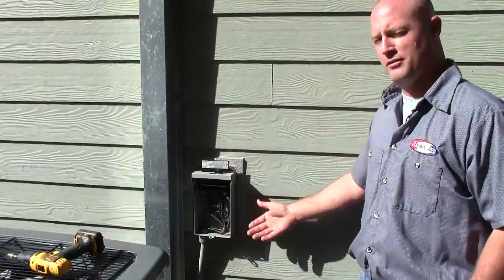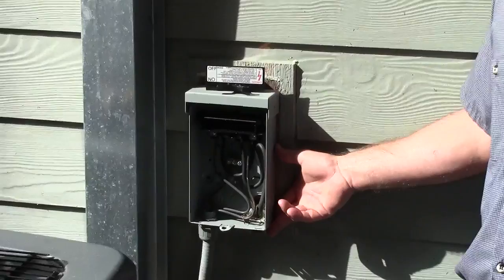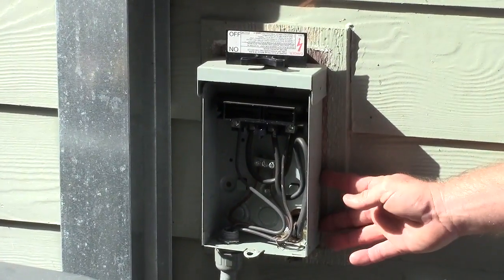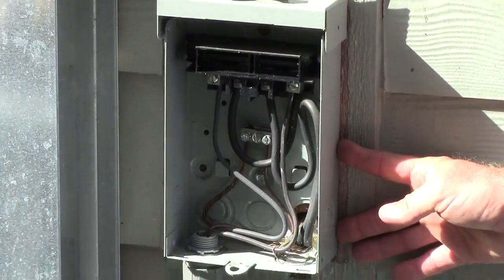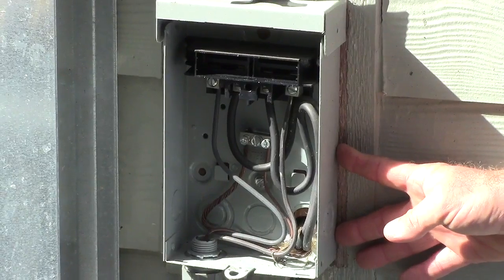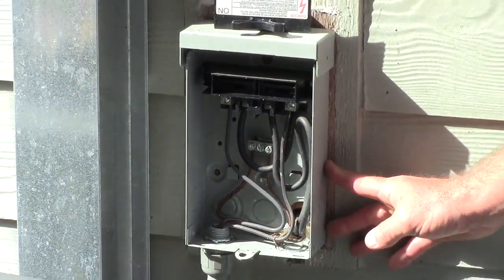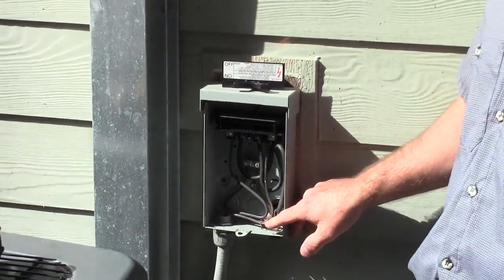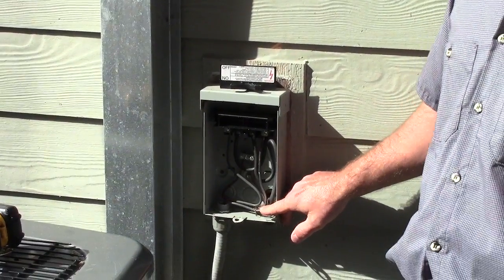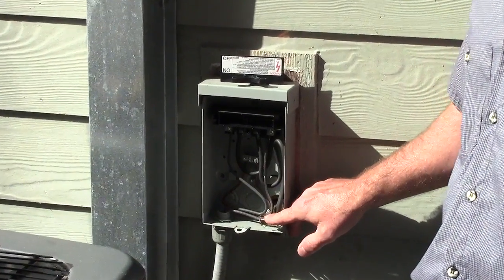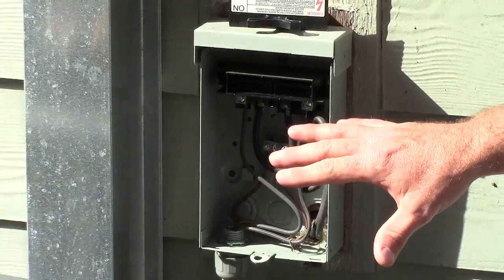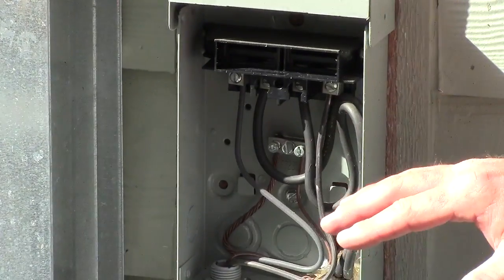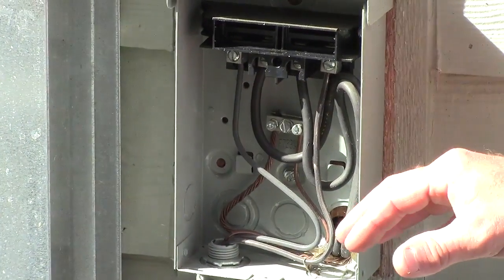This component here is often overlooked by many of the other air conditioning companies. This is a disconnect box, which most houses have on them. You should have something outside for turning the units on and off. A lot of the technicians will not open these and look inside them. This is equally as important, to make sure that all these electrical connections are clean and tight, or you will have problems in here in the future.